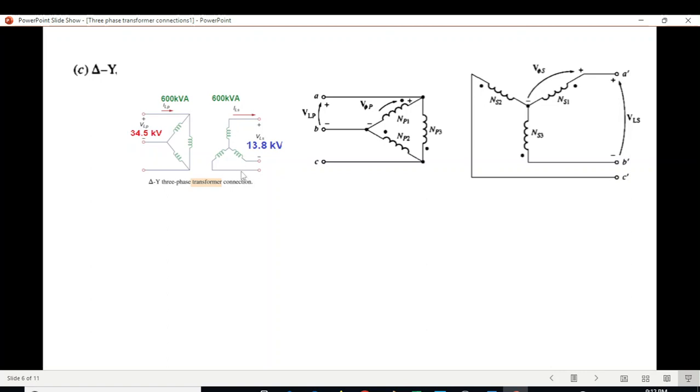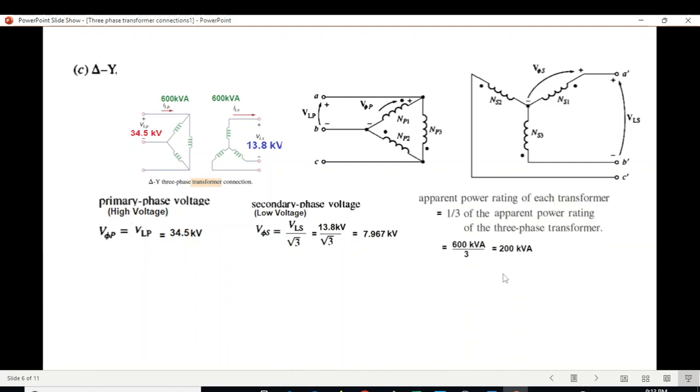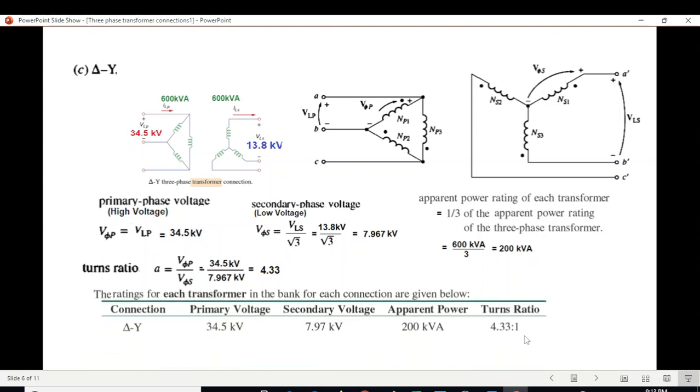Part C is Delta-Y. In Delta, the primary line voltage and phase voltage are the same, so 34.5. With Y on secondary, phase voltage is 13.8 divided by √3 equals 7.967. Power remains the same, 600 divided by 3. Turn ratio we can calculate as primary divided by secondary equals 4.33. In tabular form we write this entry.